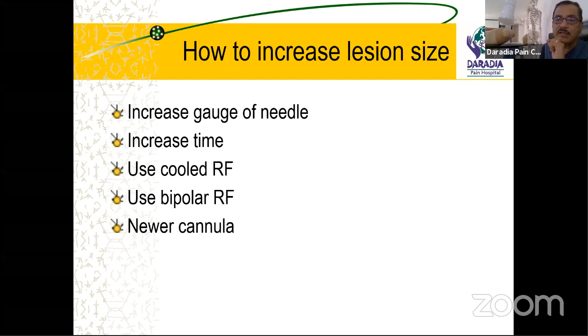If you're using bipolar frequency, or if you're using the newer cannulas, like protruding electrodes, like the Venom electrode, like the Trident electrode, then also you might have a larger size. These are monopolar electrodes. When you're using the Trident or protruding electrode, you are using monopolar radiofrequency, but still you are having a larger size lesion because your needle tip is bifurcating and you are covering a wider area. So this is how we can increase the size of the lesion.